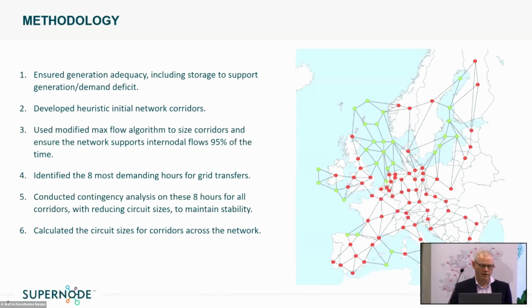So we picked the 8 most demanding hours using 2019 weather data - you can use any year. We conduct a contingency analysis for those 8 hours, because when the network is stressed, that's when you need it to stand up for the most onerous situation. And we gradually reduce the circuit sizes from the size of the corridor down to the circuit size that would maintain security of supply at all times. That was really the objective of this exercise.